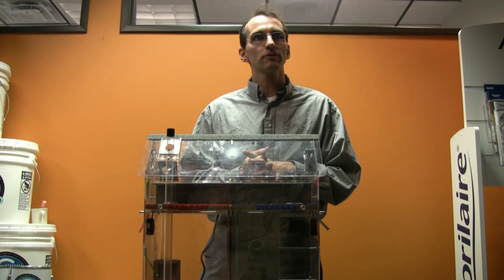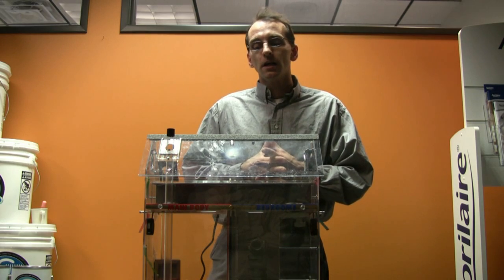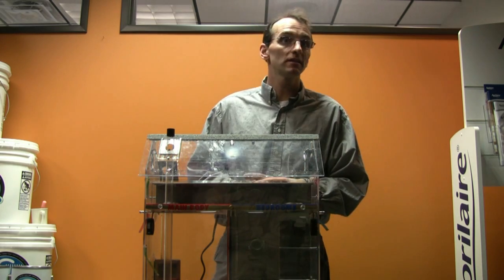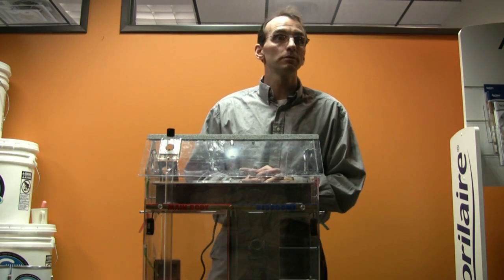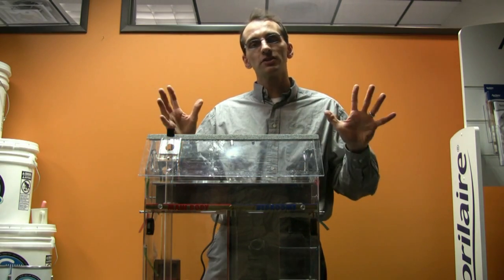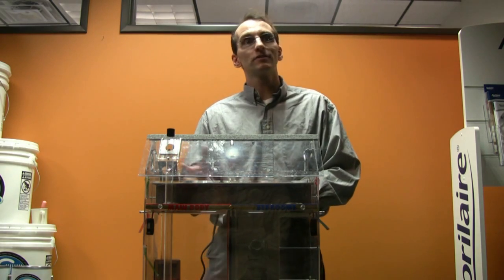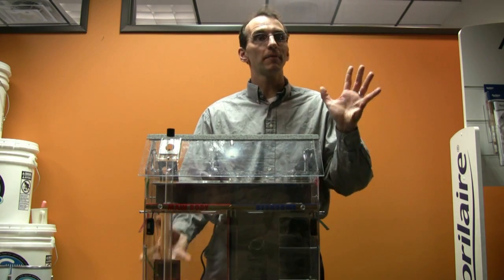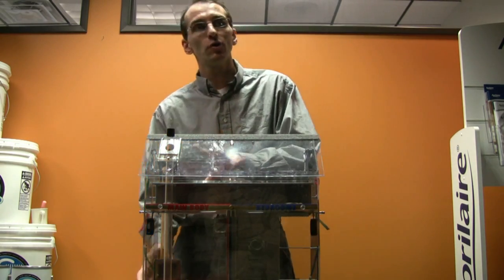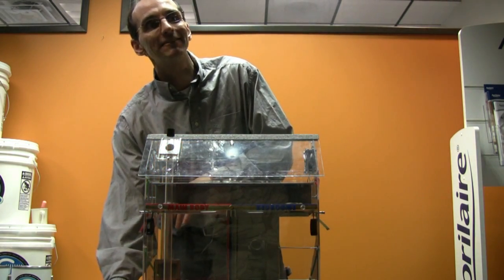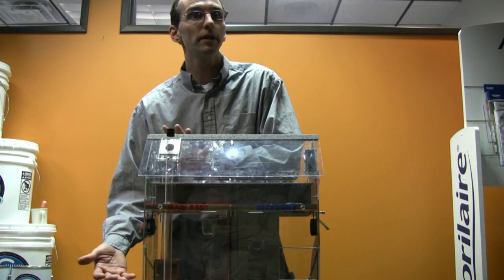The ASHRAE standard. Dave, we're assuming that ducts are in conditioned space right now, or you consider... We're not even talking about whether the space is conditioned or not. We're just talking about within this envelope. We're just talking about airflow right now. We have no stack effect, which being conditioned space or not might be affecting. As we said at the beginning, if this was a real home, we probably would have started already negative down here just because of the stack effect, but we didn't have that as a beginning point.